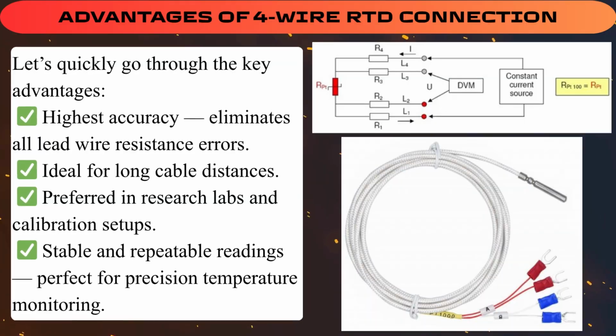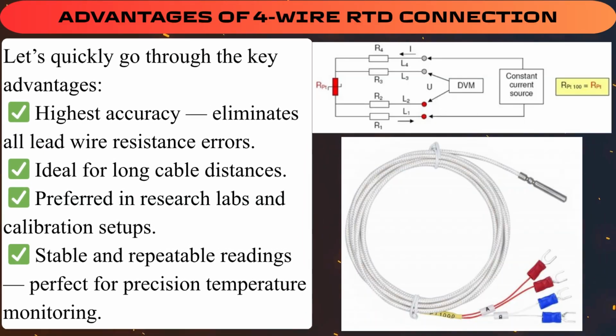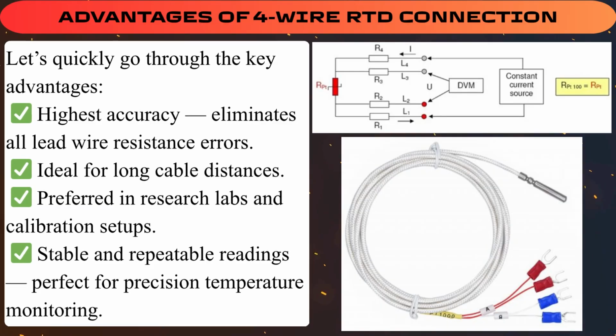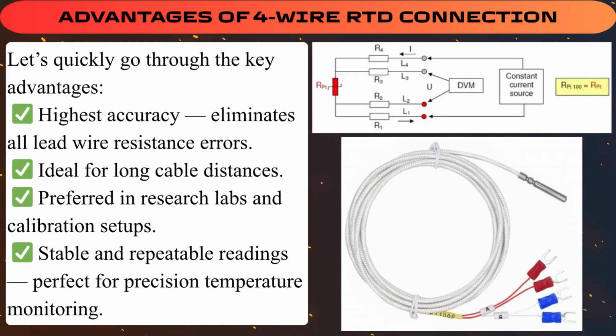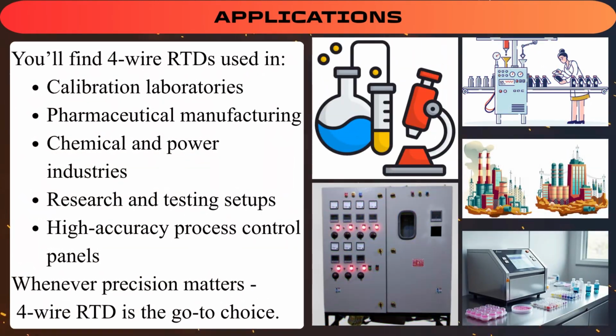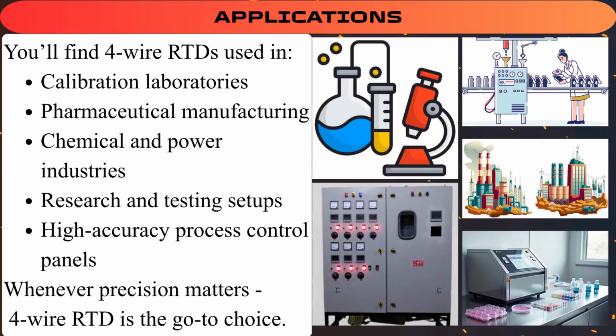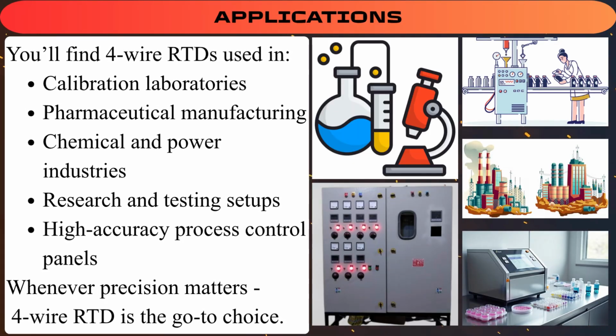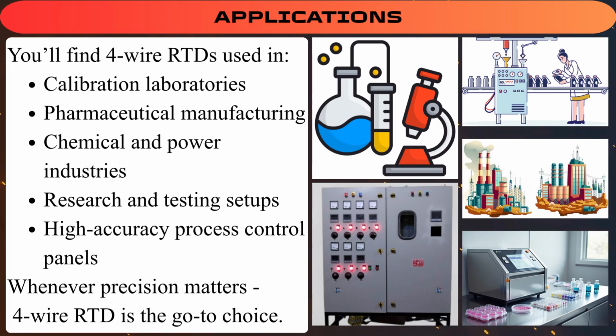Advantages of 4-wire RTD connection. Let's quickly go through the key advantages. Highest accuracy, eliminates all lead wire resistance errors. Ideal for long cable distances. Preferred in research labs and calibration setups. Stable and repeatable readings, perfect for precision temperature monitoring. Applications. You'll find 4-wire RTDs used in calibration laboratories, pharmaceutical manufacturing, chemical and power industries, research and testing setups, high-accuracy process control panels. Whenever precision matters, 4-wire RTD is the go-to choice.